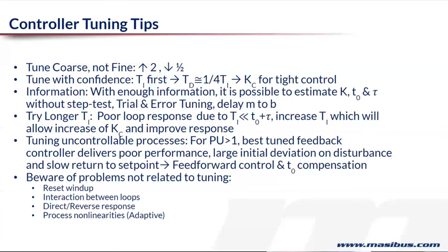And you should have the confidence to know that this will work. So observe the Ti of the process, make your controller Ti equal to that, make the controller Td 1/4 of the Ti, and then keep changing the P band or the P gain to get an acceptable level of control, right? Very simple.